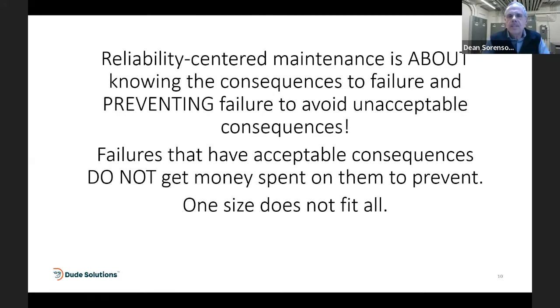That can be exampled in a master-slave pump arrangement, where you may be using this type of system to move hot water around to heat your facility, with a spare pump. That might cause you to perform much of your maintenance on a reactive basis, because once the pump fails, you have a spare to rely upon and you'll just fix the failed pump.